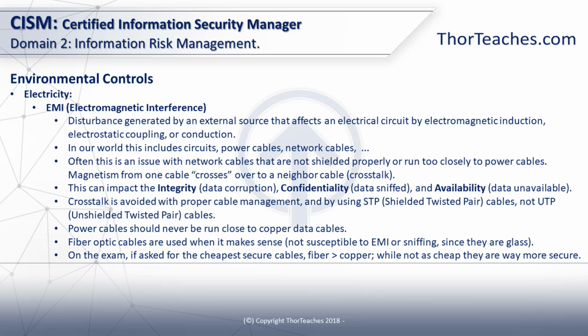Let's look at the definition first. It's a disturbance generated by an external force that affects an electrical circuit by electromagnetic induction, electrostatic coupling, or conduction. In our world, the electrical circuit that it affects could be our circuits, our power cables, and our network cables. This is most often the case with our network cables if they're not shielded properly, or if we run them too close to power cables. The magnetism from one cable can cross into another cable. That's what we call crosstalk.